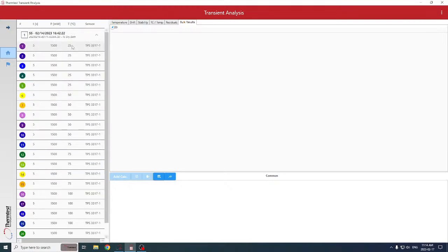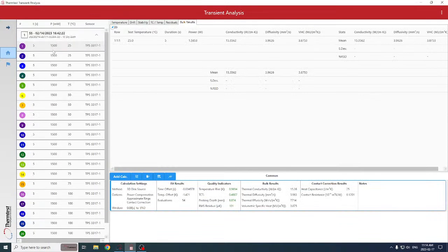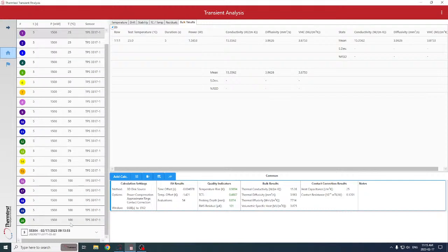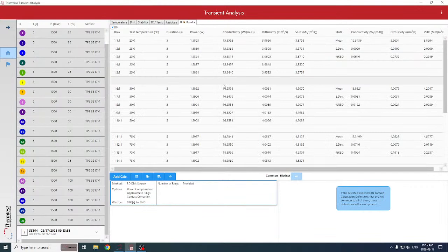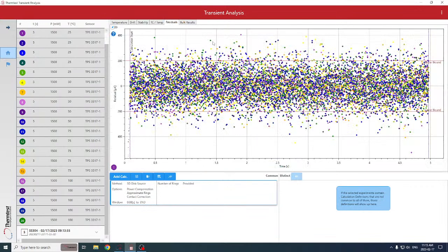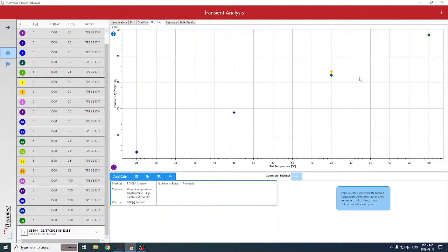So although we can see data here, we can review the data a lot more conveniently inside the transient analysis application. So here is previously run data, stainless steel 304 measured from 25 degrees, you can see this column is Celsius, up to 100 degrees. We can review the tabled data. We can also review the residual patterns, which look very good. They should be random, which means they're free of contact resistance and free of reflections due to hitting the boundaries of the sample. But we also can look at the thermal conductivity with temperature. So here you can see the change in thermal conductivity with temperature up to 100 degrees. So each of these are five experiments, I believe. You can see the change in thermal conductivity with temperature for stainless steel 304.